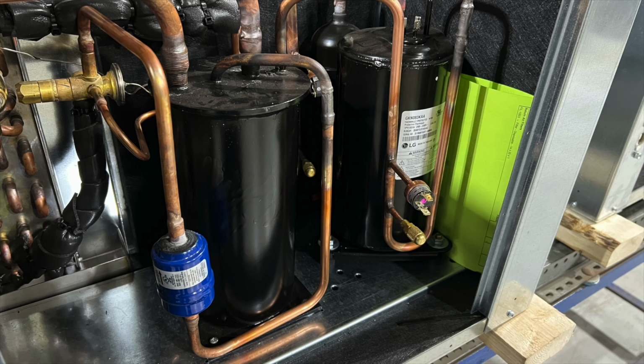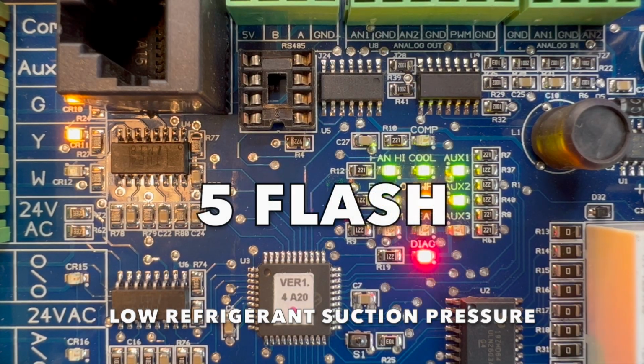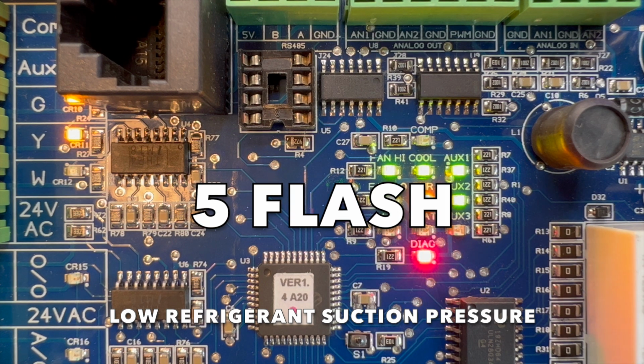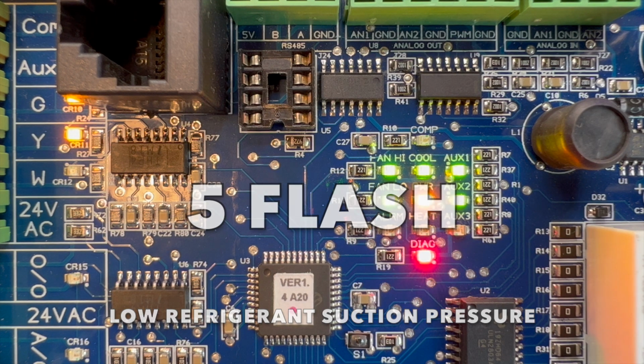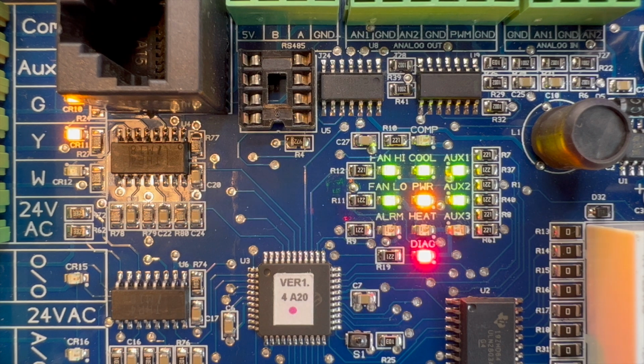High head pressure with a cool liquid line is a sure sign there is air in the refrigerant. Recover, evacuate, and recharge. 5 flash, low refrigerant suction pressure. There is no hard lockout for this fault. The low pressure switch trips out when the suction pressure drops below 60 psi and resets when the pressure goes above 90 psi.